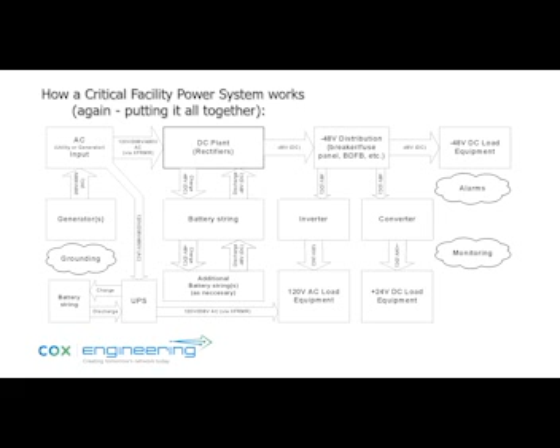So we want to have a backup and redundancy mindset: A and B feeds. Now sometimes they're not redundant, but they should be. You want true load sharing if you can, N+1 redundancy. You want the stuff never to go down. And you also want any changes, maintenance, grooms, adds, whatever, as well as any power work, to be transparent to the customer.